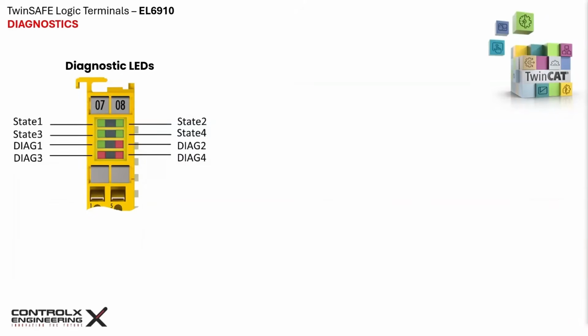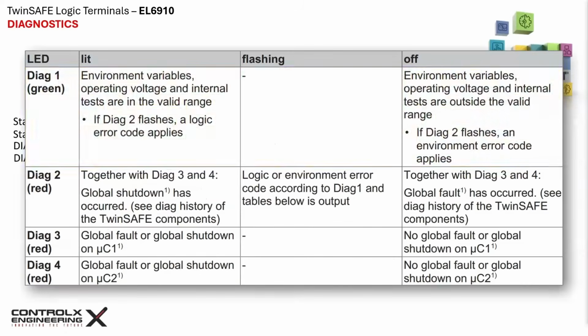Out of the 4 diagnostic LEDs, only diagnostic 1 LED is green and the other 3 are red. This LED indicates if the operating voltage and results of the internal tests are in valid range. If it is off, then the exact error code is indicated by the number of flashes on the diagnostic 2 red LED. This table lists all possible fault types. Diagnostic 3 and 4 LEDs indicate fault states of both of the internal microprocessors. Ideally, you want all red LEDs to be off.